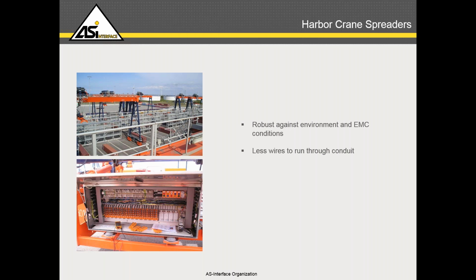ASI is a big component for many of these manufacturers because it's very robust against outdoor environments and EMC conditions. A big benefit is being able to run a single two-wire cable up to the control arm of the spreader to bring all the I/O back to the system. Those are the major reasons this industry chooses ASI for wiring.